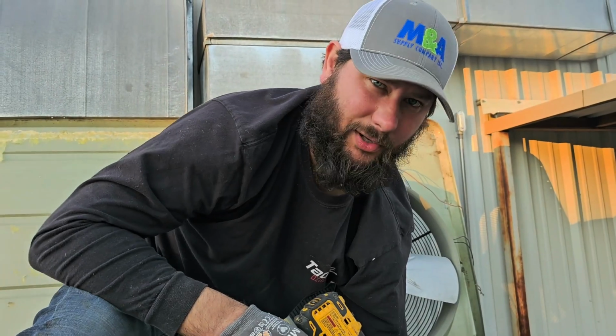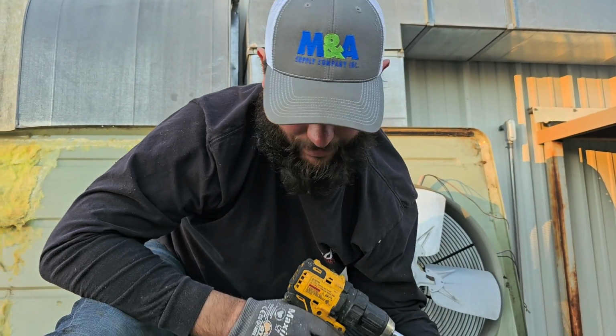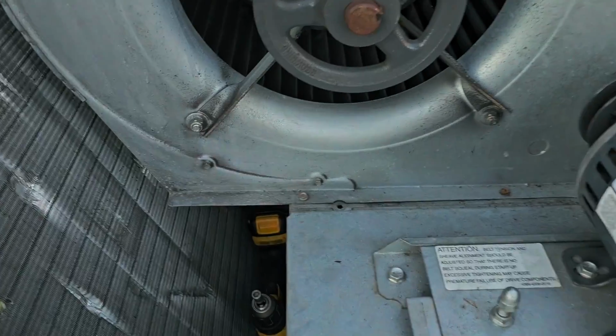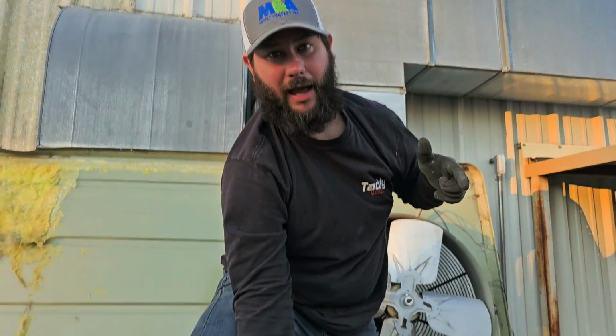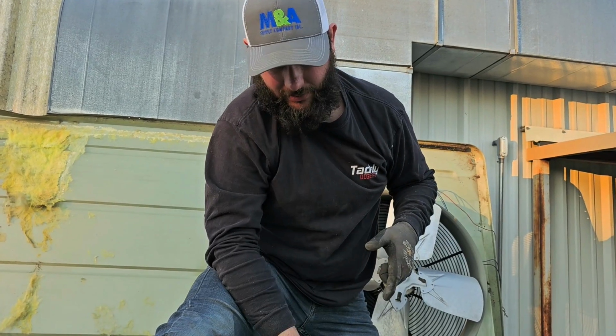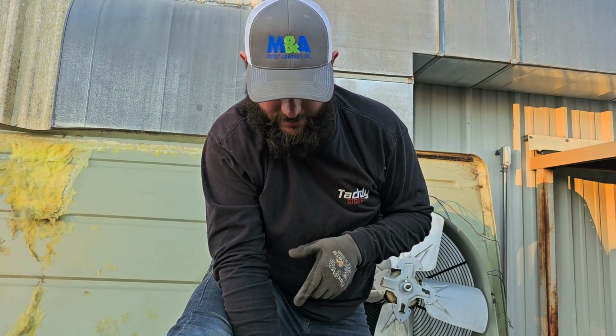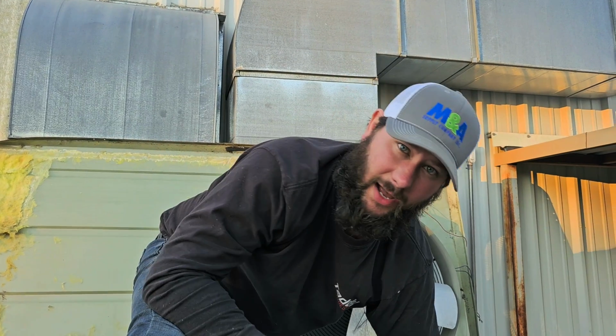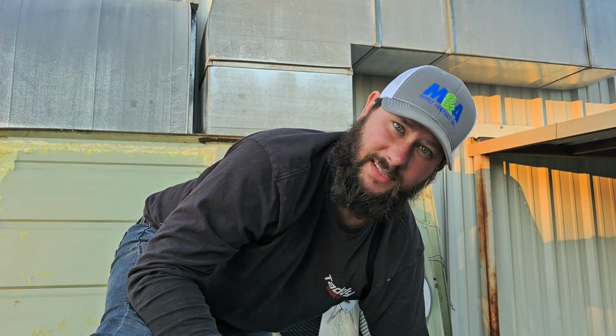The one thing about the blower housing and getting it in here is there's a lip on the very back of this blower housing. So when you go to put it in, you have to tip it back this way and put that lip in. Once that lip is in, then you can push it forward and it'll set in place, but it won't go down unless that lip is inside.